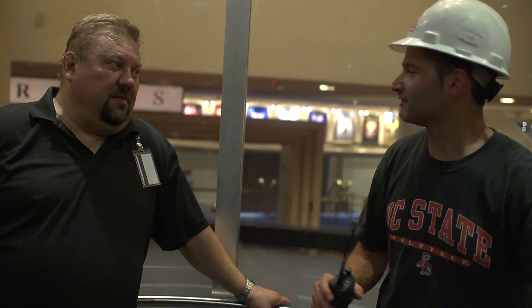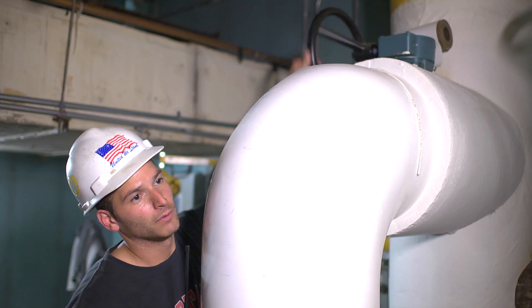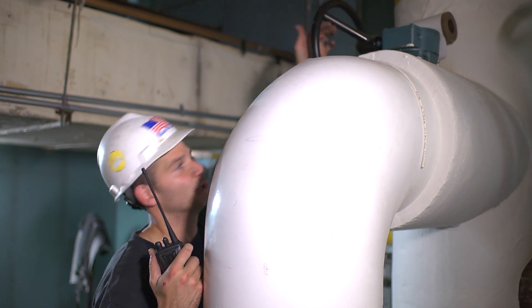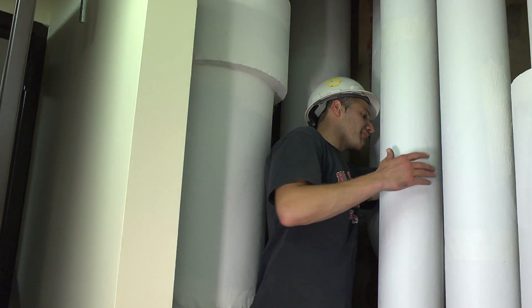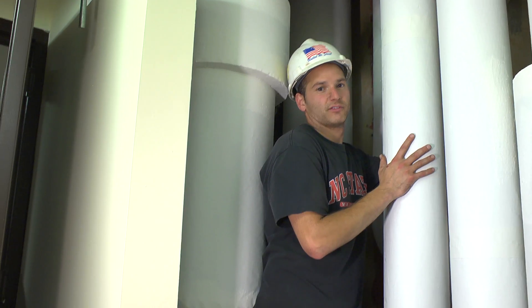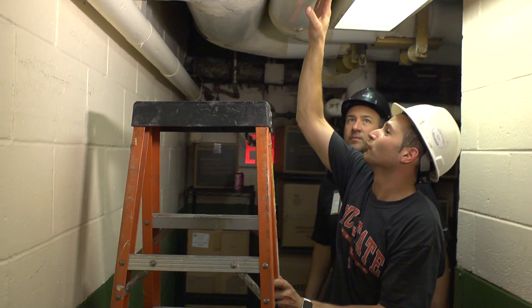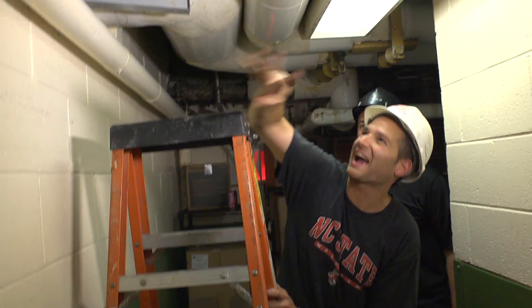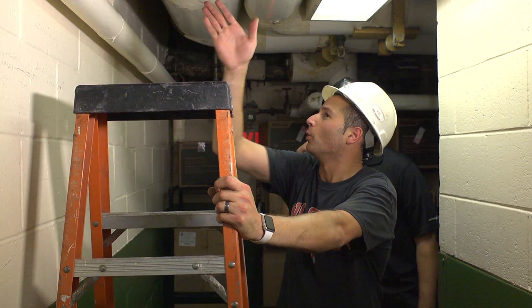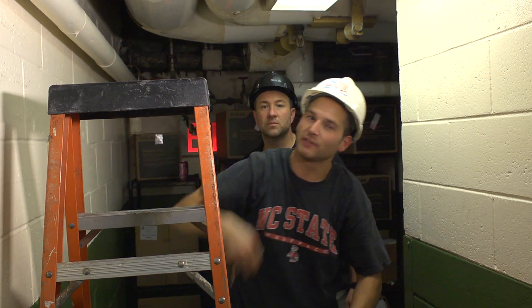Right now when I start bypassing, it's eating the steam up. I'm sure this is going to take most of the steam. This valve is to feed the kitchen equipment, the new riser for the kitchen. Right now this is full of steam. We don't want it full of steam because now what we're doing is sending the pressure and the flow back this way up. So what we have to do is stop the valve there, open the other valve to the riser, then we're going to go on the second floor and divert those valves to back feed the system, because this floor is different — it wasn't like every other one.